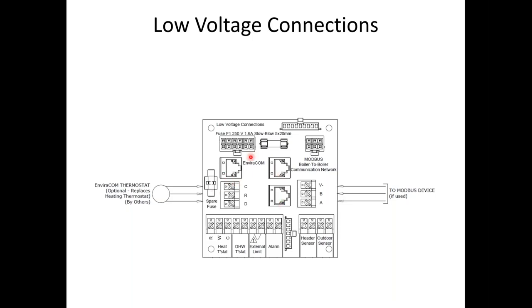The boilers are going to have 3 plugs on the front of them that will accept Cat 5 cable. One will be for the EnviraCOM. If you were using the Sage panel, this is where the Sage panel would plug in. The other 2 are going to be your Modbus ports, which will be for boiler-to-boiler communication. With the onboard controls for these products, we can link up to 8 of them together with no extra controls. It can be done via Cat 5 cable or 3-wire thermostat wire, V, B, or A. In order to do multiple boilers, you would need to wire the header sensor in. If you don't have the header sensor, it will not allow you to enable a master.